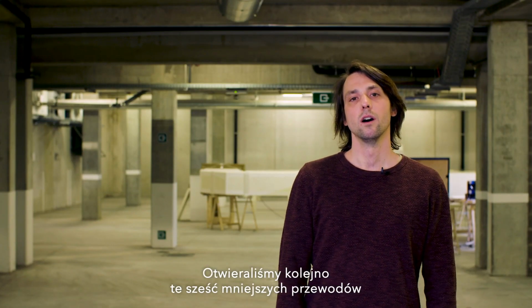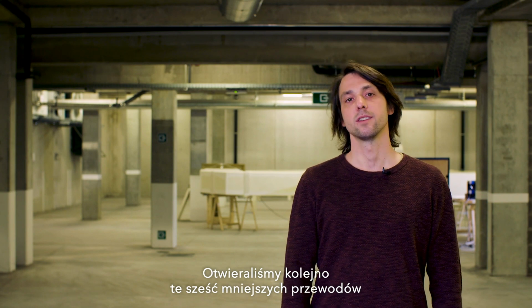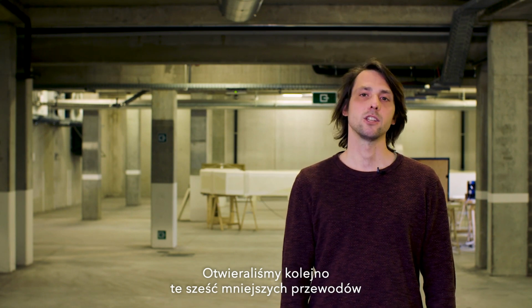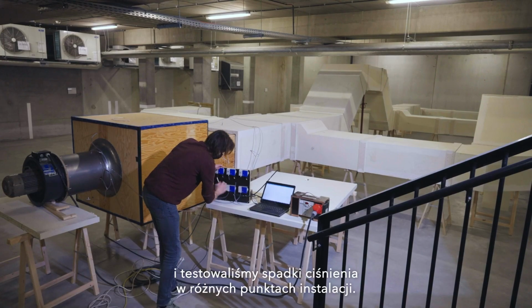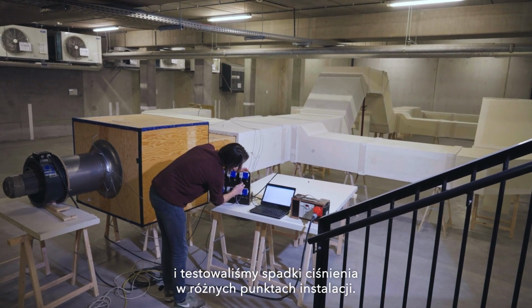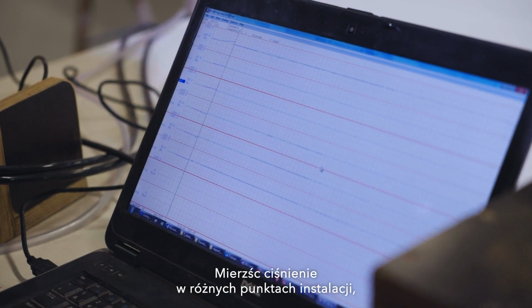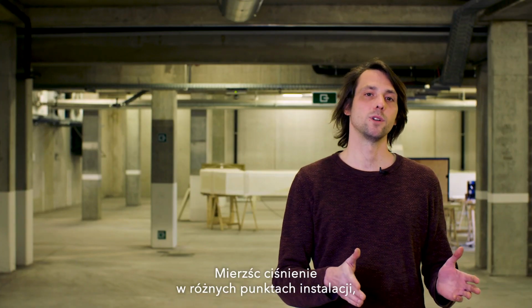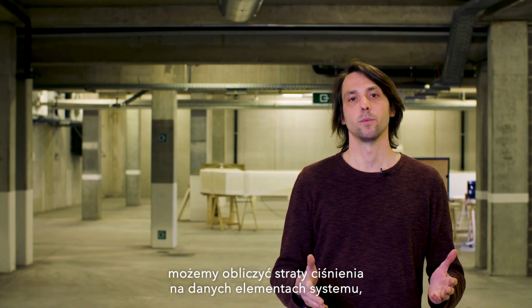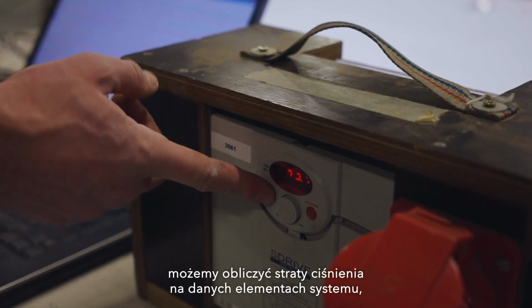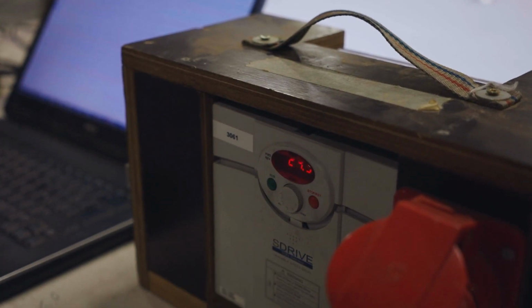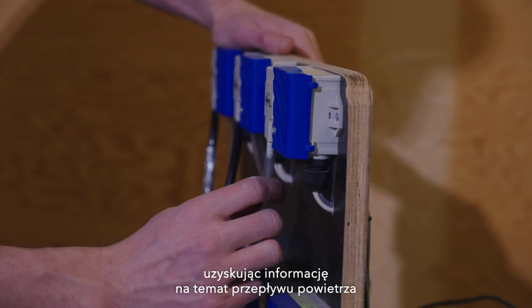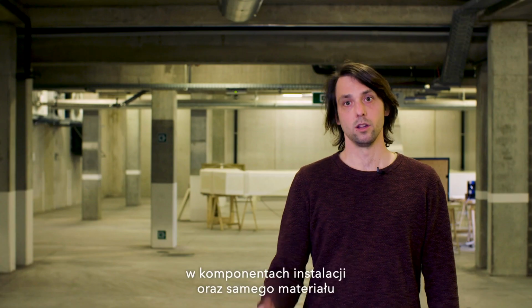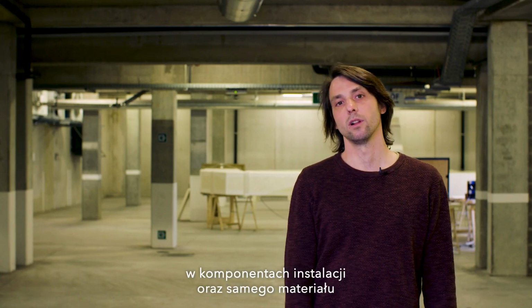We opened all 6 of the side channels one by one and did pressure loss tests at different points in the network. By measuring the pressure at different points, we can calculate the pressure loss over certain elements, which tells us about the flow resistance of the components and the material itself.